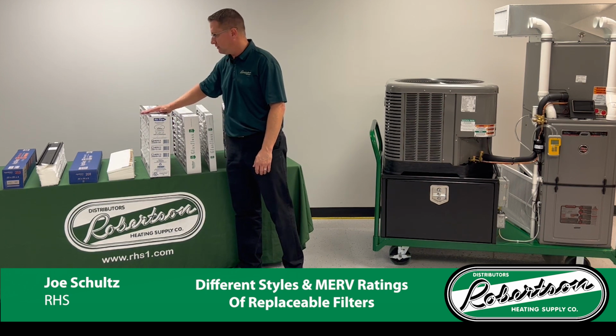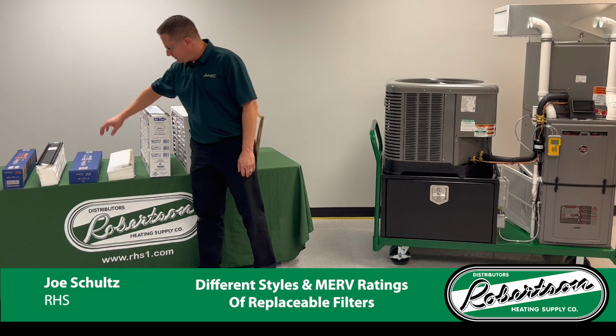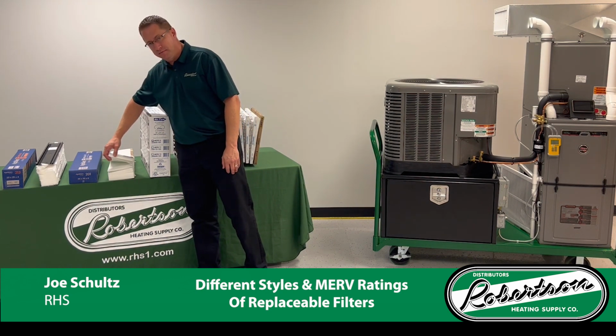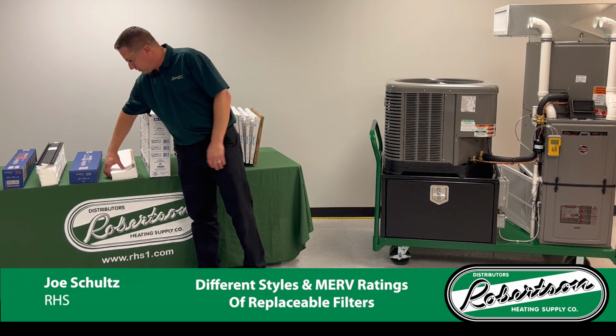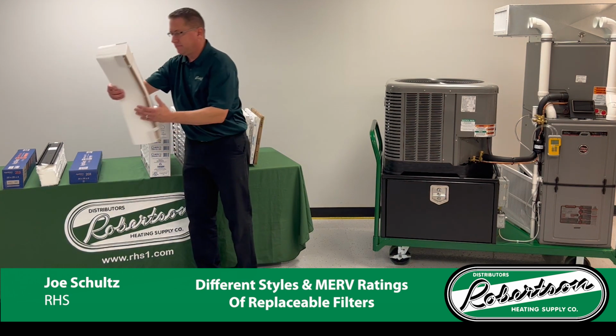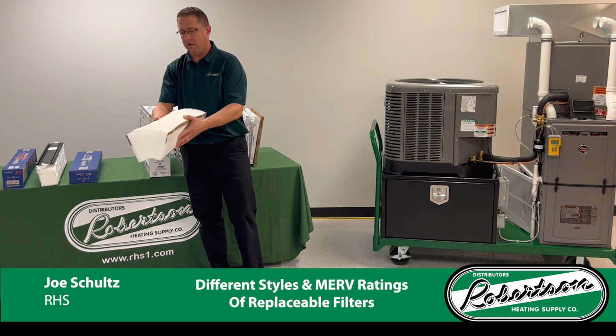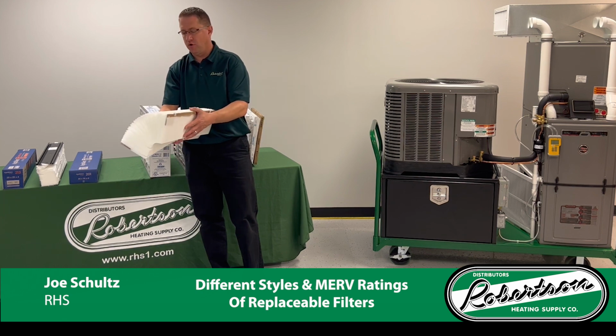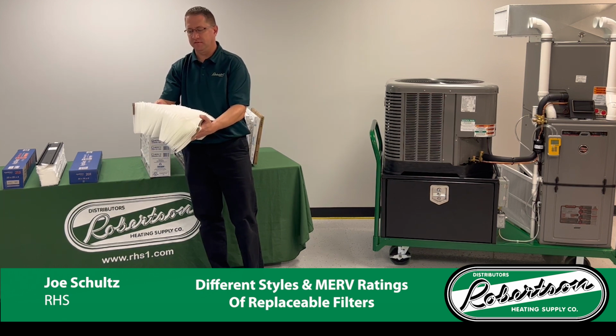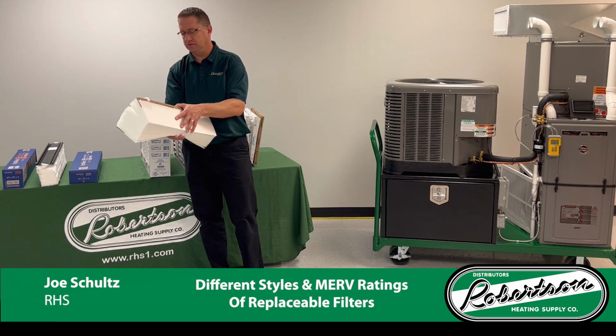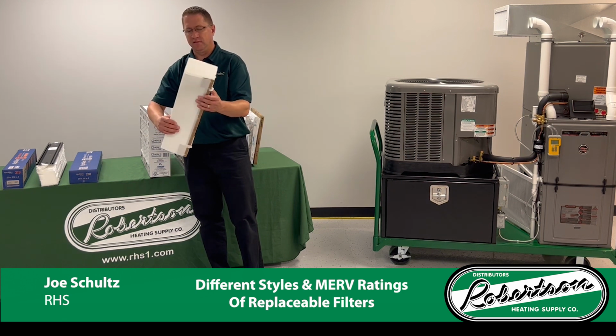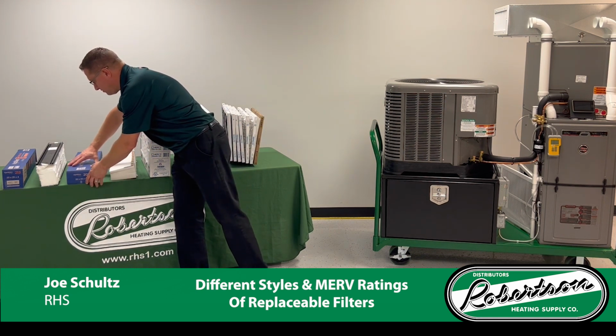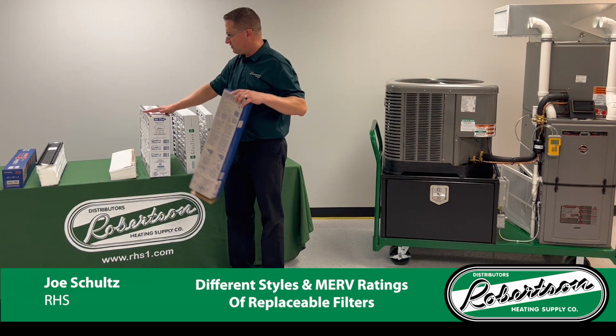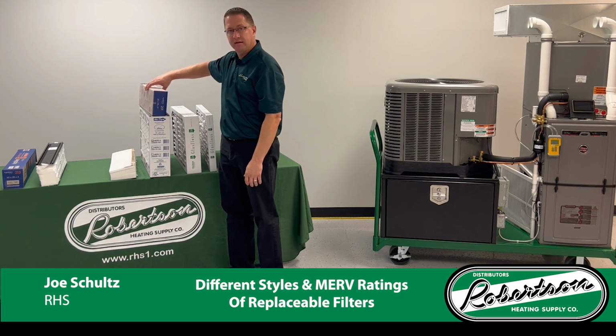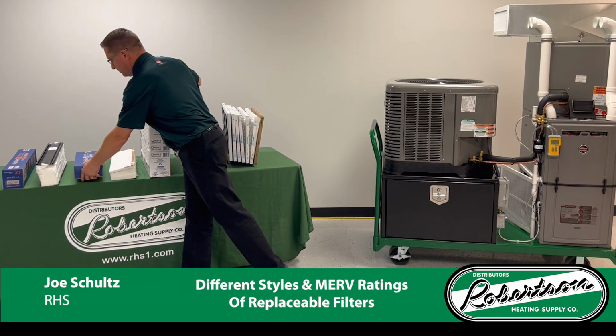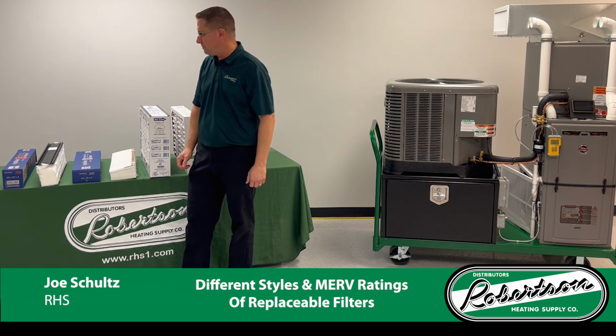360 degrees around it. The next style filter is an expandable media filter, and the expandable filters are what some people call accordion filters. So they actually go into a plastic housing or a metal frame, and there's combs that separate these and keep these pleats equally distanced apart to capture dust, to space out the filter correctly. These are nice because the box fits in a very, very small frame. You get the filtering of something like this, but in a package of this size. So it's easy to keep on trucks and service, and it just takes up less space.